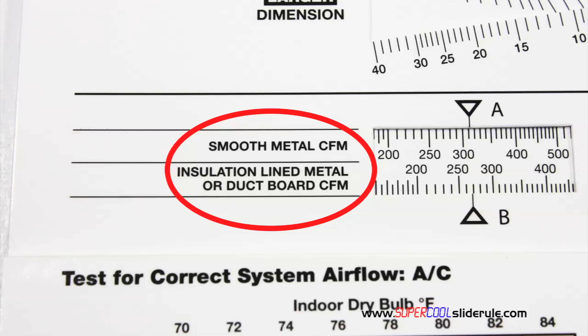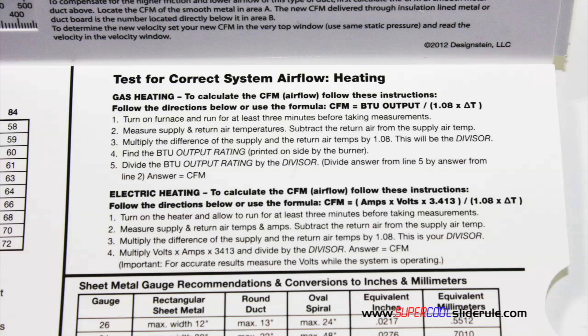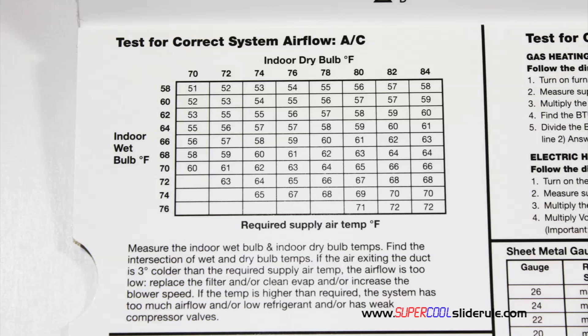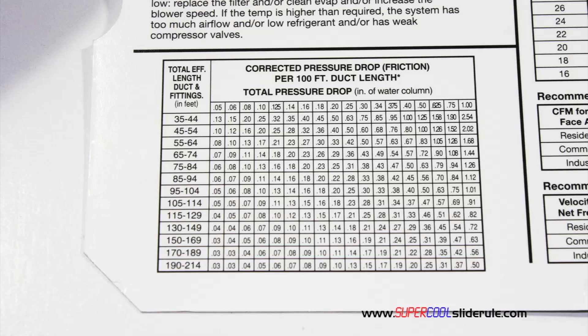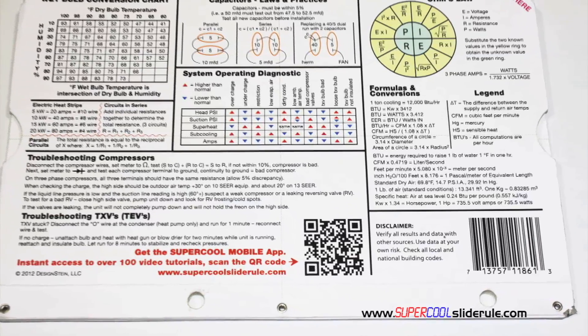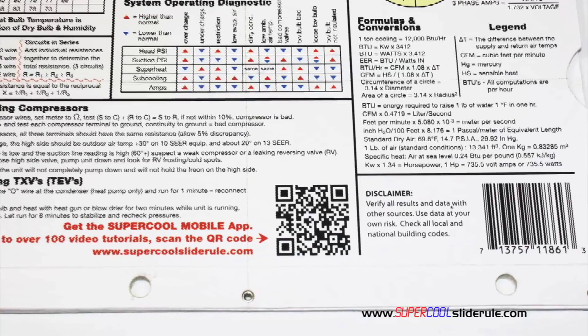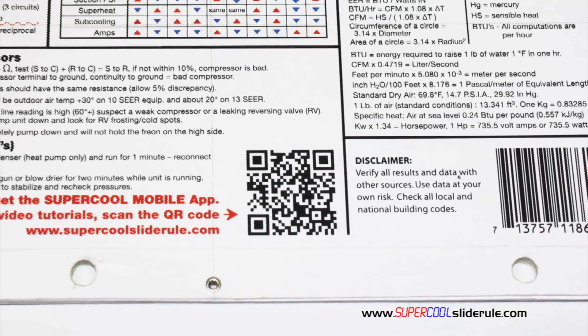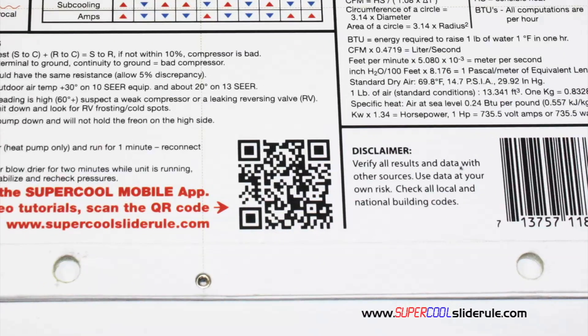The majority of technicians have never been taught that if the insulation is on the inside of the ductwork, you cannot size it with a regular duct calculator. It has step-by-step directions for determining airflow through a gas furnace, electric furnace, or an air conditioning unit. It has pressure drop multipliers for ductwork, as well as recommended velocities. And finally, scanning this QR code gives instant access to over 100 tutorials to assist the technician with every test and repair imaginable.